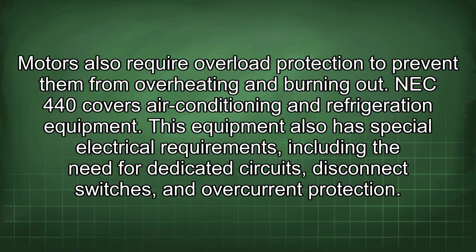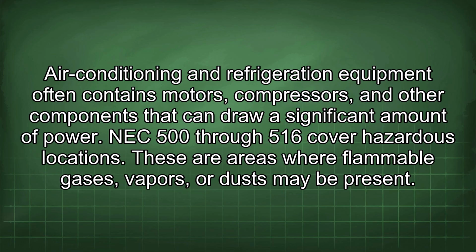NEC 440 covers air conditioning and refrigeration equipment. This equipment also has special electrical requirements, including the need for dedicated circuits, disconnect switches, and overcurrent protection. Air conditioning and refrigeration equipment often contains motors, compressors, and other components that can draw a significant amount of power.